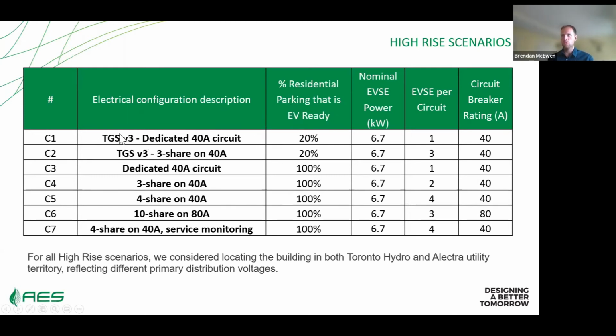The first two were meeting the current requirements of the Toronto Green Standard version 3: one with dedicated 40 amp circuits to each parking space for 20% of all parking spaces, and one with 3 share on 40 amp to 20%, which is allowed for in version 3.